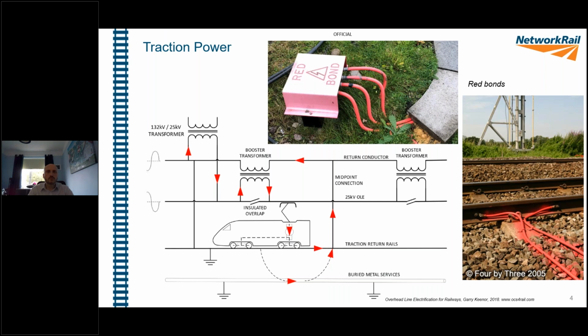From there, we still need to have that return circuit. So typically the way is using the steel wheels themselves to create an electrical connection to the running rails, where we utilize one of the running rails as our return path. From there, we have features known as red bonds, highlighted red because they're an important feature, because they are what are completing the circuit. Without these, we can have the overhead line fail, or the power distribution side of it fail. These red bonds connect that track to a return conductor, which is running alongside the track. It's one of the along track conductors, which ultimately then returns back to the transformer at the feeder station.